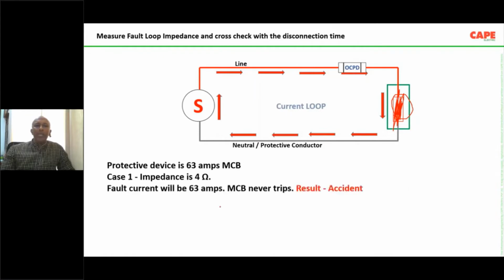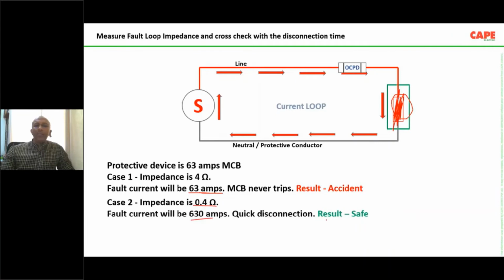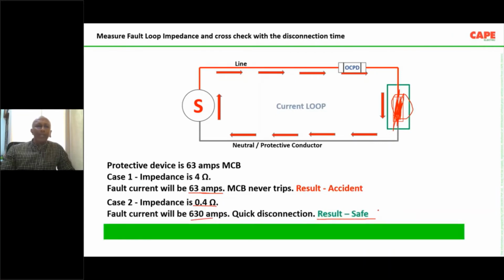determines the current. Imagine you have a 63 amps type C MCB and the impedance of the loop is 4 ohm, then the current is only 63 amps, and your MCB will never trip. Now in the second case, if the impedance is 0.4 ohm, then the current is 630 amps, and your circuit is safe.